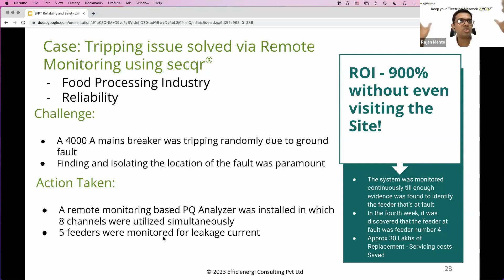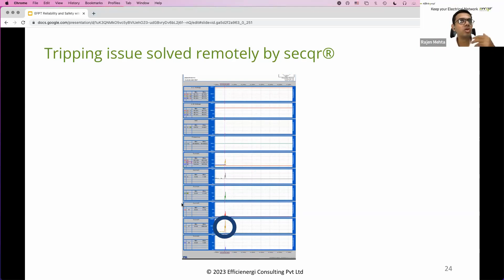The image may not be very clearly visible, but what you see over here is an 800 ampere zero-sum current spike which occurred during the 3rd week of our monitoring, and we were able to isolate from where this was coming. The customer was able to deep dive into that particular feeder, that particular load, and find out the insulation failure which had occurred and the reason for the ground fault that was coming. Otherwise, it was just a shot in the dark for them.